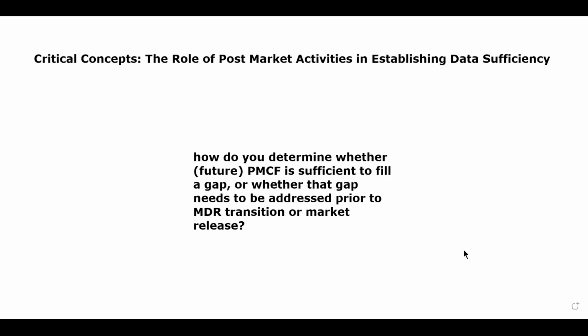How do you determine whether future PMCF is sufficient to fill a gap or whether that gap needs to be addressed prior to MDR transition or market release? And Sarah, would you like to take this one? Yeah. I think in this case, you want to make sure that the way you have designed your plan is anticipating any potential complication that could arise in the future as a result of your test, any reason why your test or your device may not perform as intended. So as you're developing your PMCF, you want to ensure that you're searching for these potential complications proactively and reactively.